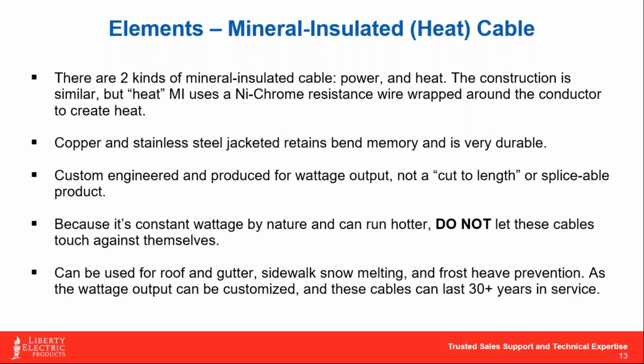So we have the one with the resistance wire that creates heat. The best way I can describe an MI cable is that it's very similar to an electric element used in your oven, like the element in the bottom of an electric oven that's twisted into all kinds of funky shapes. The outer jacketing of an MI cable is either copper or stainless steel, and we tend to go with copper when we can, because it's much more malleable than stainless steel and it's also less costly per foot.